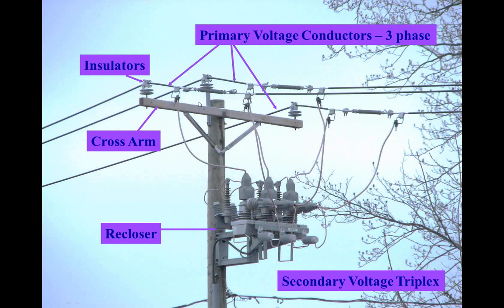Here's a typical pole. This is a complicated pole, but this is typical. If you notice, your primary conductor is up here on top of the pole, and it's being held off the cross arm by this insulator. This insulator has got to keep that conductor from touching the wooden cross arm. If for some reason there was a car versus pole hit, and that insulator failed and dropped that conductor onto the wooden cross arm, that cross arm is going to become energized. The pole is going to become energized. And if somebody looks around and says, oh, all the wires are still up in the air, it's safe, you can get out now.